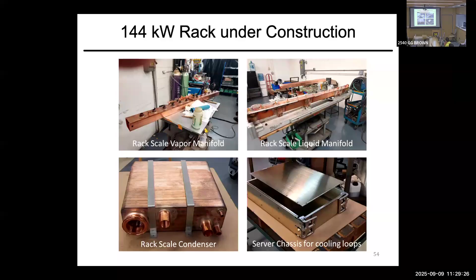The difference between this and other technologies is that this rack has everything - the condenser, all the elements - it's rolled into the data center and you plug it into the primary loop. The difference from air cooling, where you get a certain delta T and then need a chiller operating, is that we can extract the heat at 70 degrees.